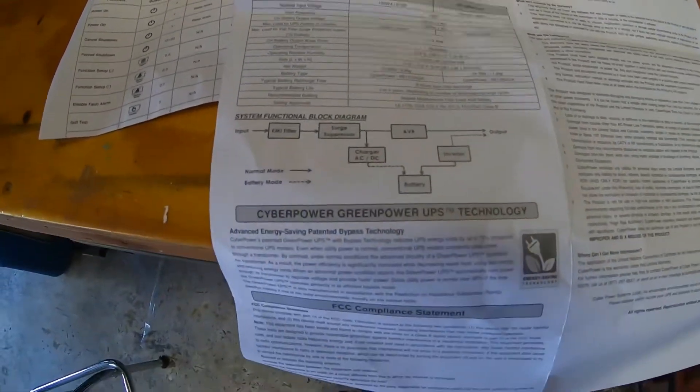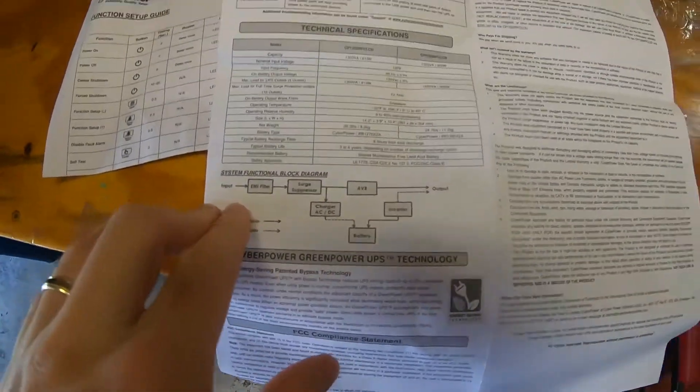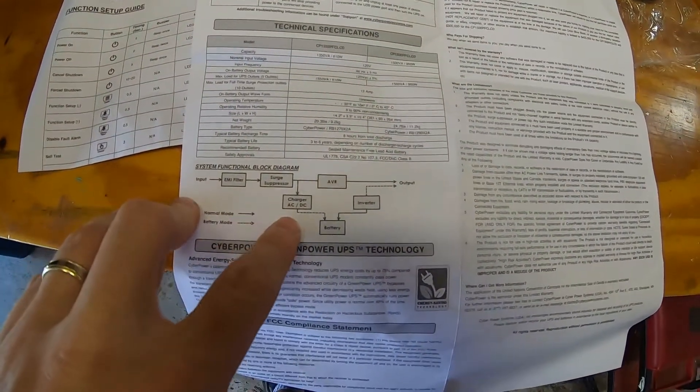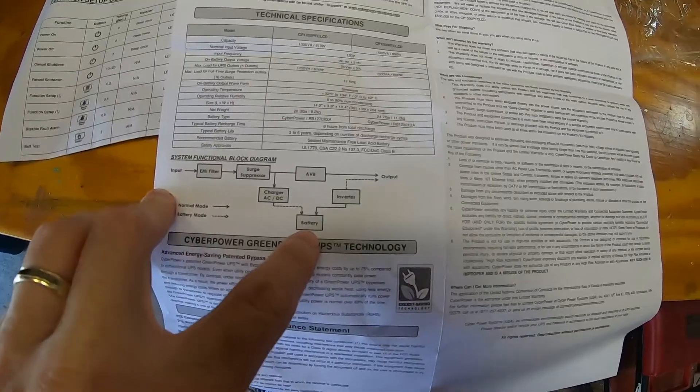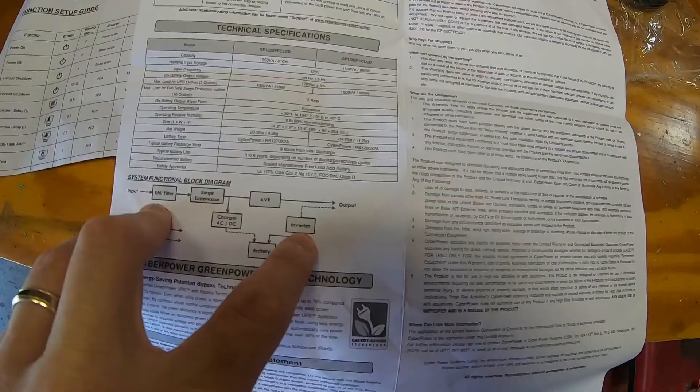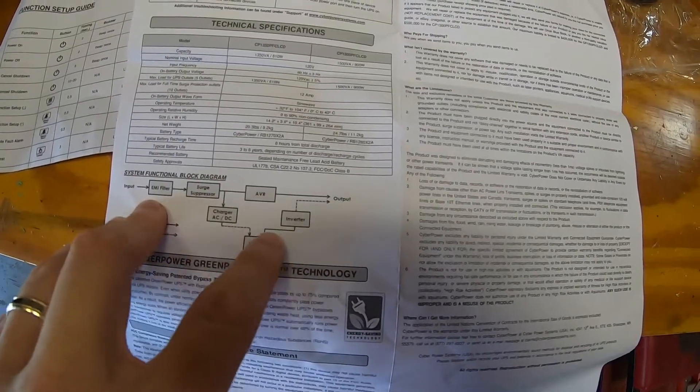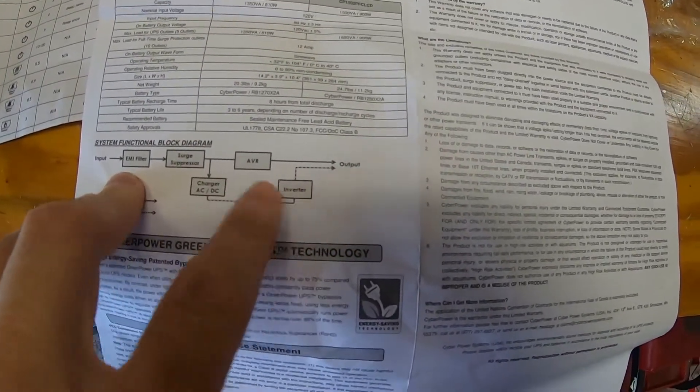And here's a block diagram here. So you have your input. An EMI filter. Surge suppression. To the charging circuit for the battery. And then for the inverter. So I guess this is really what you're paying for to get your true sine wave output.